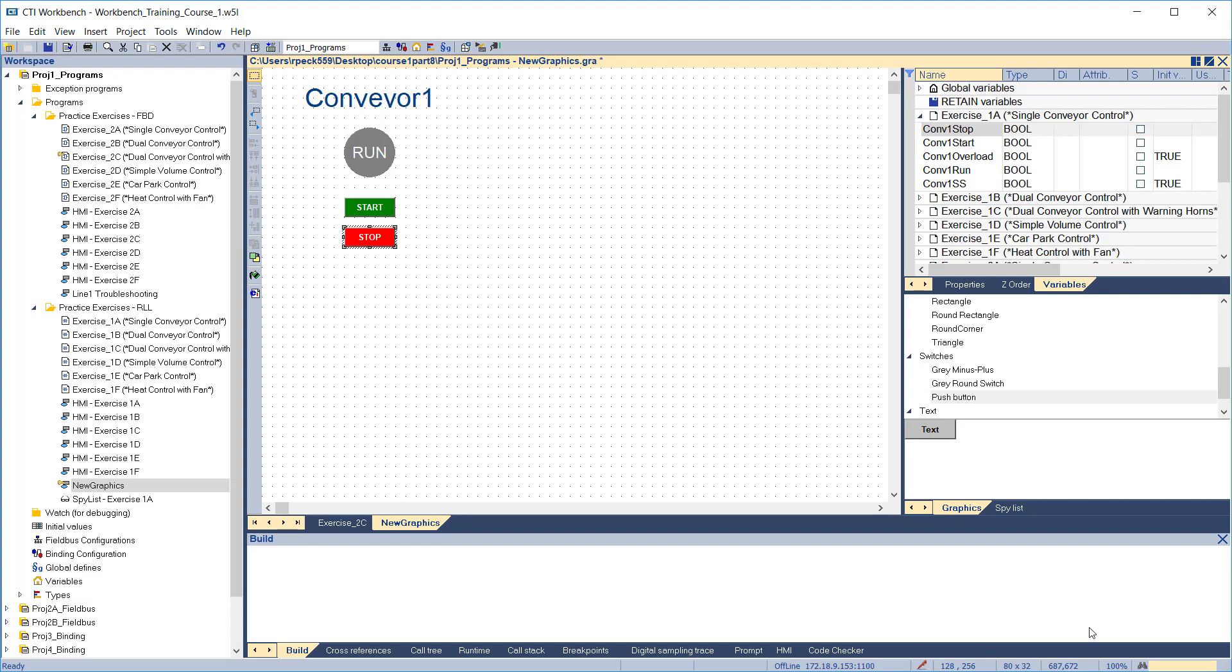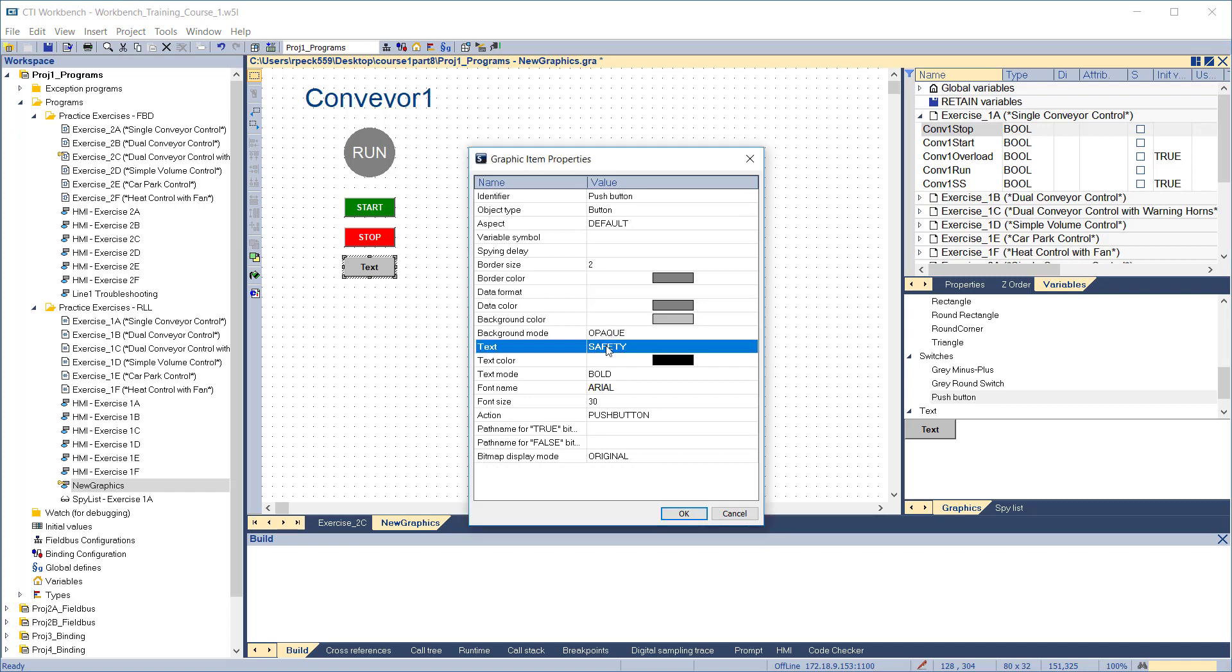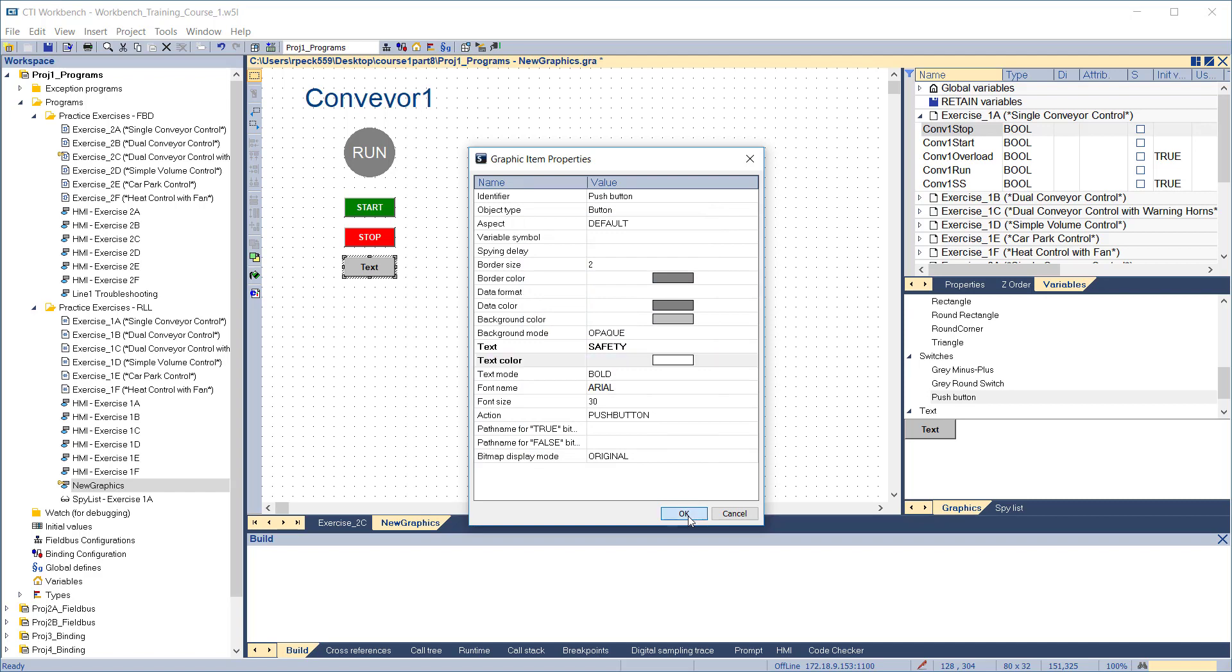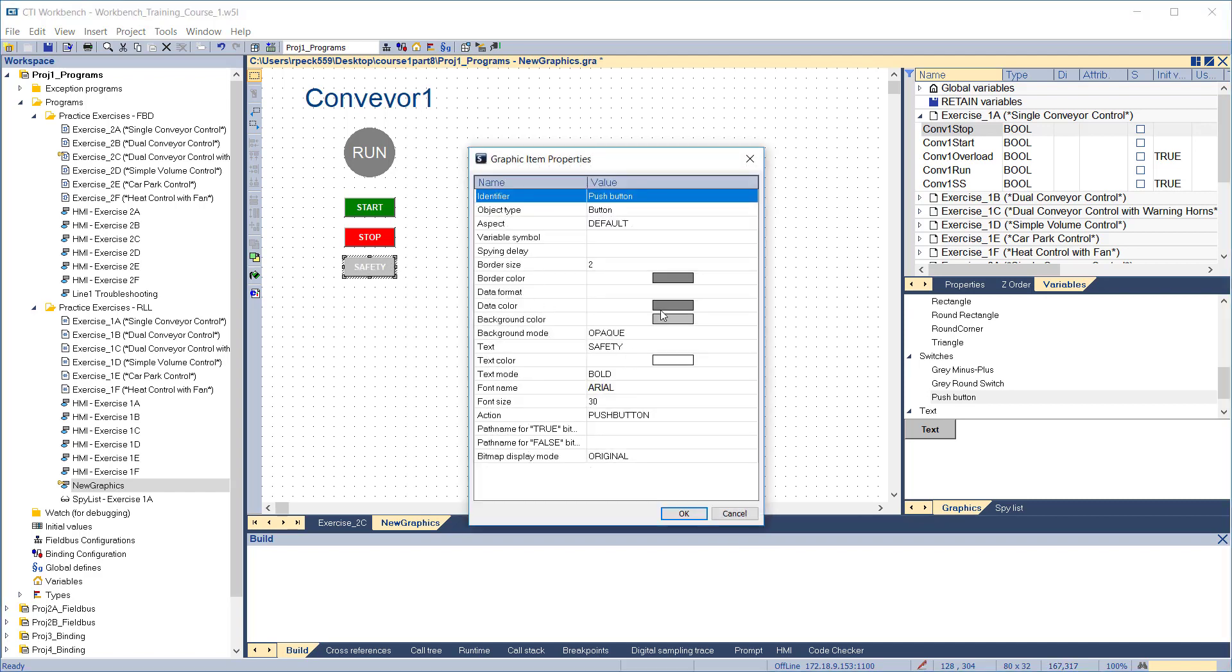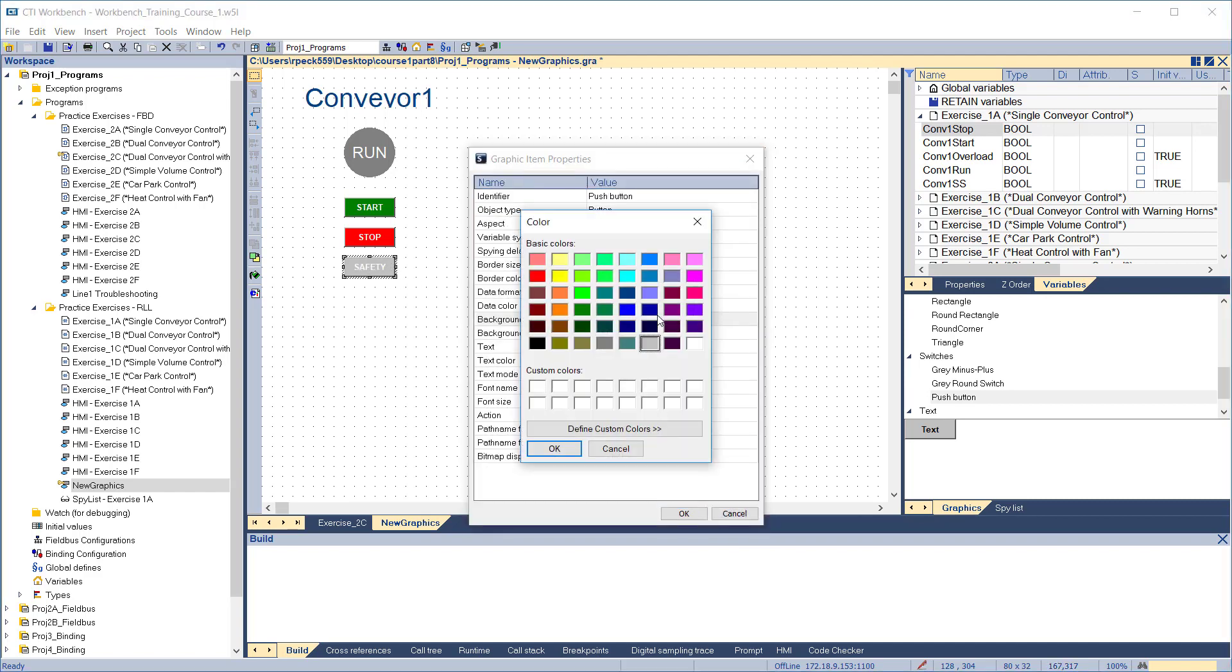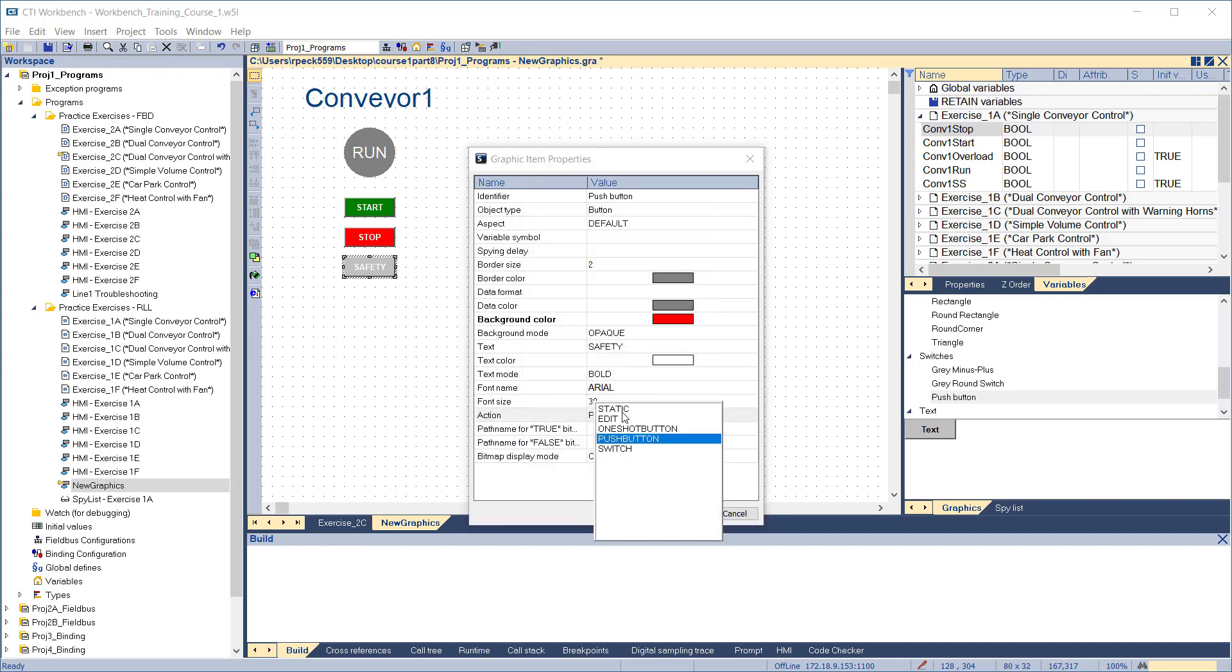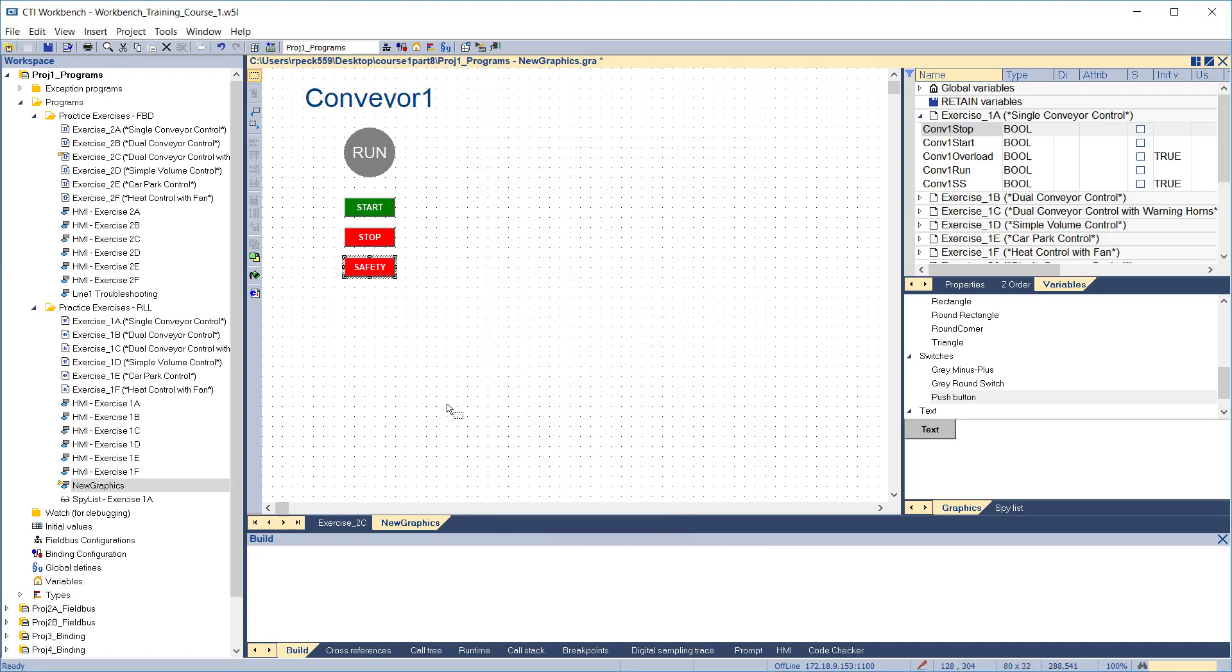Now add the safety stop. Make the background red. Change the action from push button to switch, since this input is not momentary. Click OK to exit and attach the Conveyor 1 safety stop variable from exercise 1a.